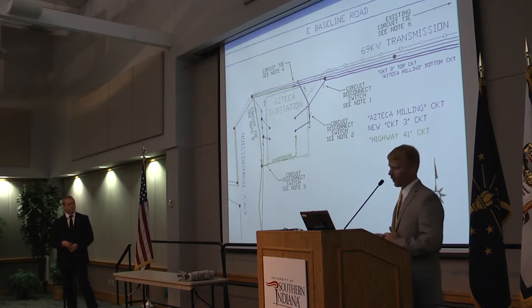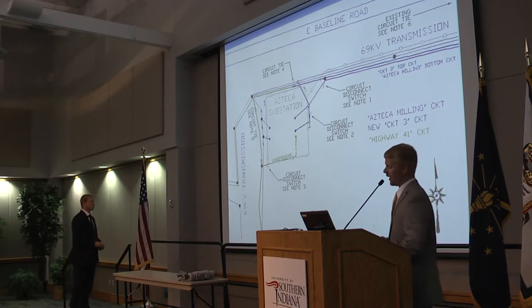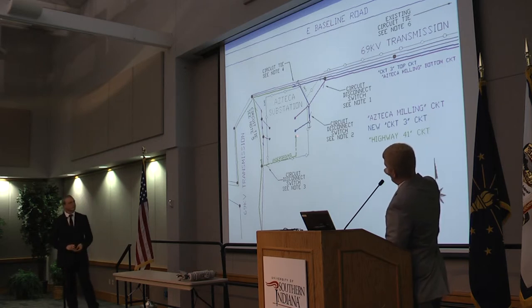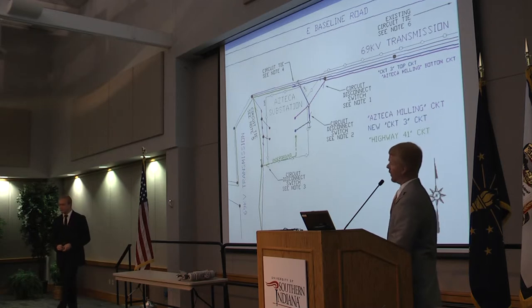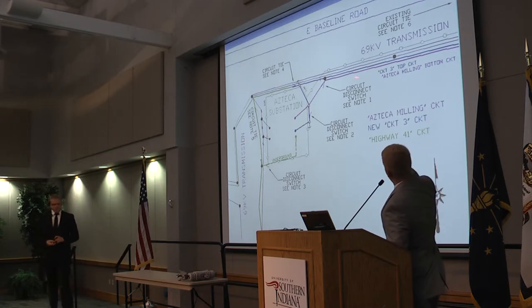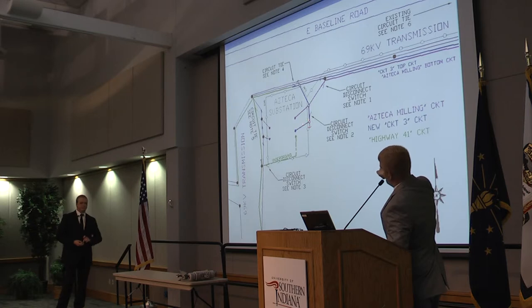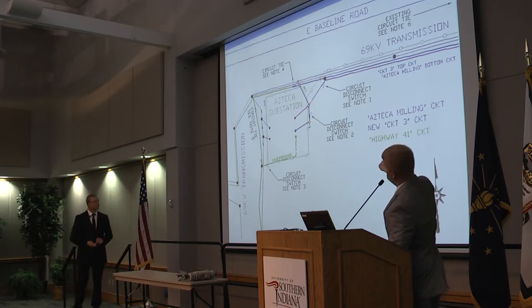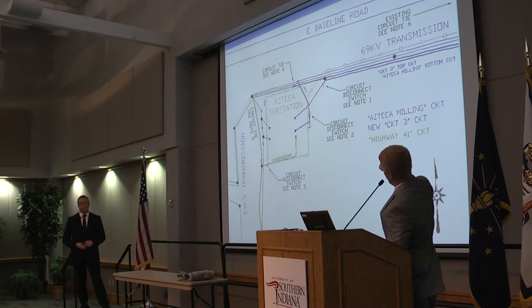This is the third circuit layout from the distribution side. This drawing shows the different paths of each of the new circuits represented by each new color. Those are called out over here. Azteca milling circuit, which will be the dedicated circuit feeding directly into Azteca, is the pink circuit that feeds up and down through here. This will be what we will call the new circuit. Even though this will be on the new set of regulators and fed from the new transformer, this will need a new name for the circuit. It will feed then the same path with new poles represented by these open circles.